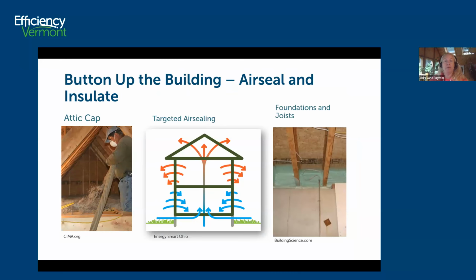So buttoning up. Everyone has heard about button up the building, air seal and insulate. Well, there's a couple of reasons why in heat pump applications you really want to do this. So your existing heating system, let's say it's baseboard hot water, baseboard hot water is like 160 to 180 degrees, and that baseboard is going underneath windows and walls that maybe are poor performers.